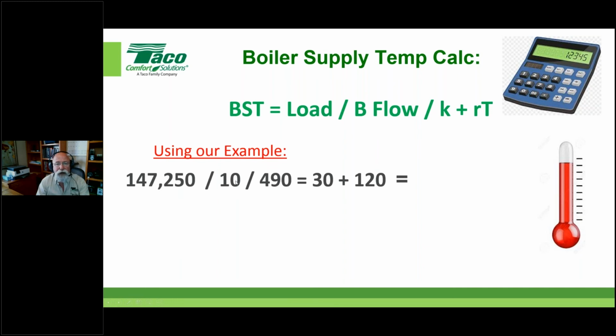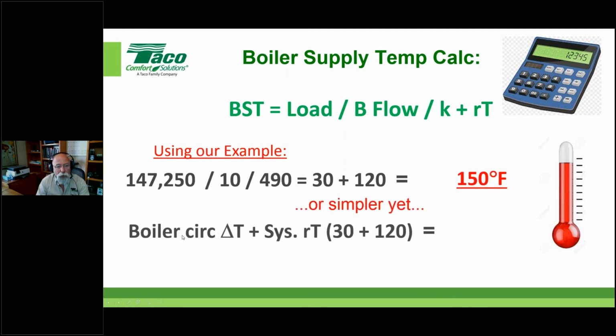147,250 divided by the flow of 10 gallons a minute. My constant's 490. It gives me a 30 plus 120. 120 plus 30 is 150. Or even simpler, you just take the boiler's delta T that you used and add it to the system return temperature. So 30 is my boiler delta T that I used, and I got a return temperature of 120. 120 plus 30 is 150.